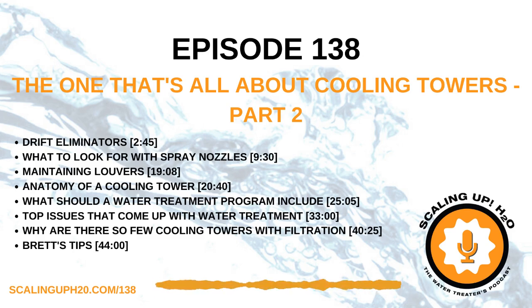It's definitely helpful when we have information from the manufacturer. I'm thinking of an account that had an issue with a variable frequency drive because they wanted to save energy. They were putting less than 10% flow through the unit, and the high concentrated solids evaporated out and were left on the fill. They said your water treatment chemicals aren't working, why aren't they working? We had to explain it was an operational issue.